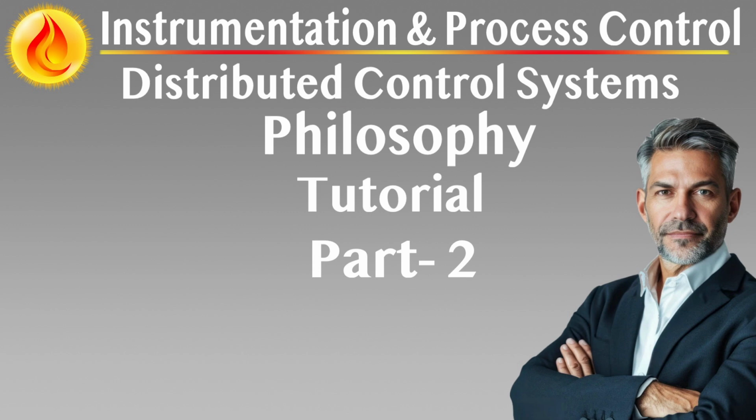Automated proof testing. Built-in proof test functions simulate faults and verify trip responses without disrupting operations. Test reports are generated automatically and archived to satisfy regulatory and insurance audits. Remote validation tools. Engineers can validate shutdown logic, test inputs, outputs, and review diagnostics remotely via encrypted connections, reducing time and risk associated with field interventions.